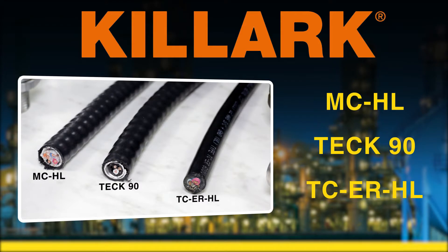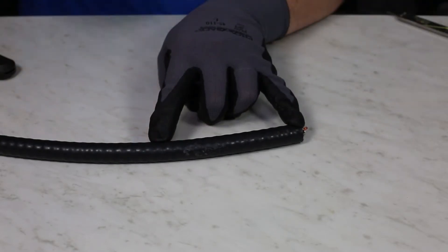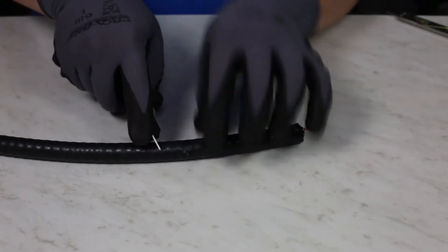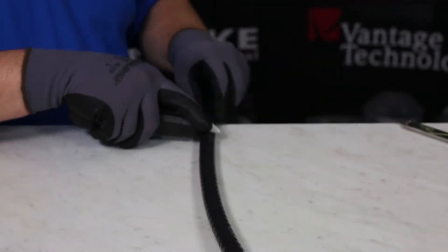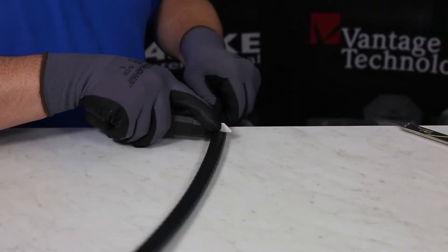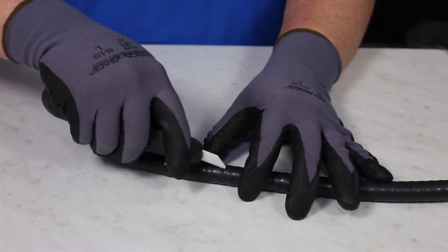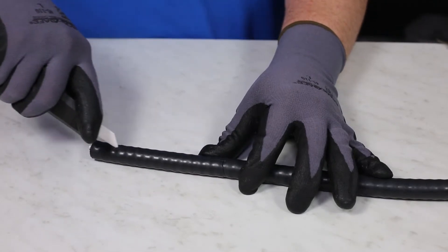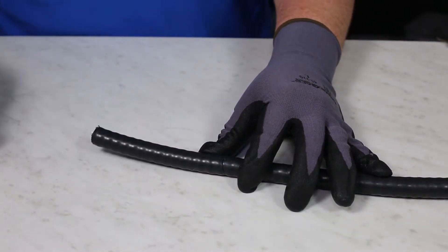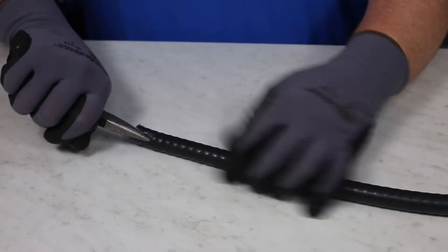When prepping TECK 90, you will first need to properly measure the length you will need to wire for your device. You can do this by using any measuring device. After the correct length is determined, take a razor knife or your preferred cutting device and simply cut through the PVC coating around the armor, completing a 360-degree cut, then cutting straight down the cable to the end you recently measured from. You can simply use your fingers or take pliers and remove the PVC jacket that you cut, exposing the armor.